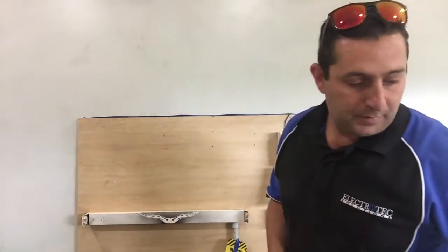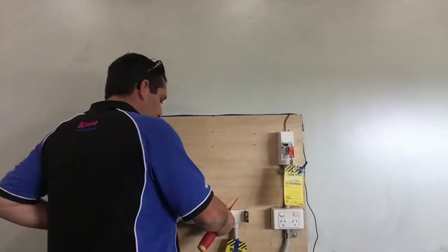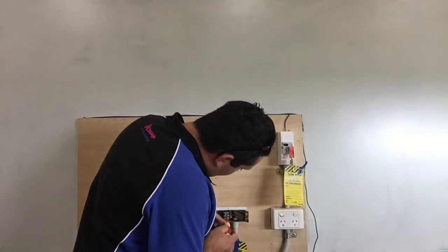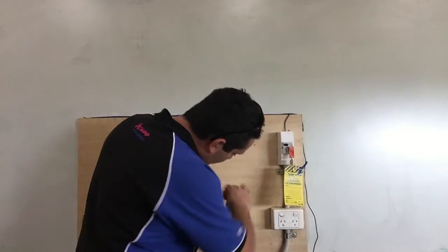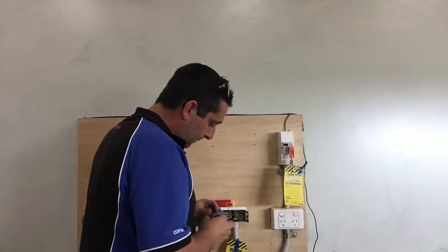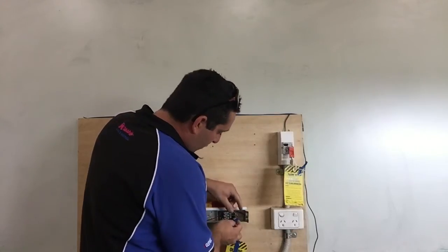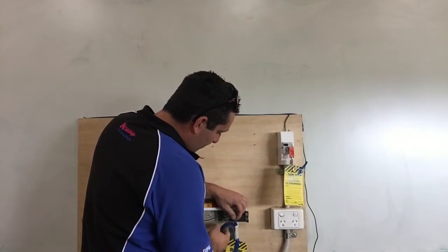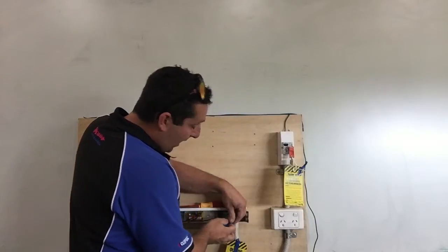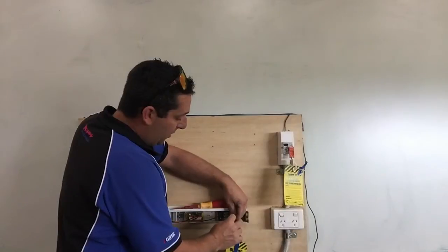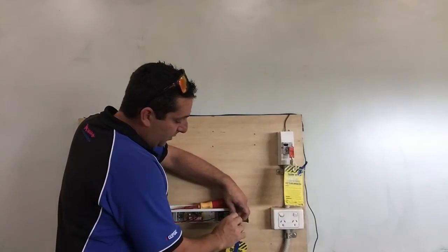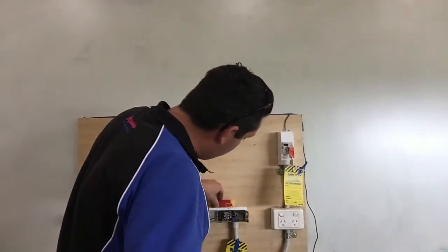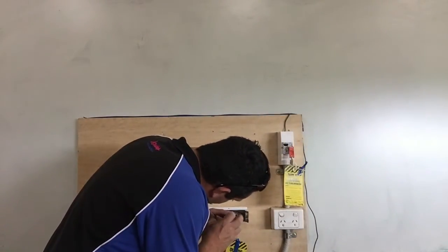Okay, now that we have our diagram, we can start by removing the conductors. Let's remove them, starting with the active. Being careful not to touch that copper onto the frame, because it can cause the RCD to trip, regardless of whether the circuit that we're working on is live or not, between neutral and earth. Next, we'll disconnect our neutral.